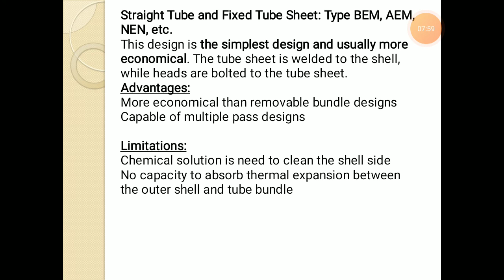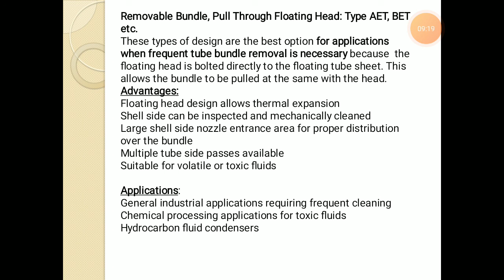Removable bundle pull through floating head type, AET, BET, etc. This type of design is the best option for applications when frequent tube bundle removal is necessary, because the floating head is bolted directly to the floating tube sheet. This allows the tube bundle to be pulled at the same time with the head. Its advantages are: floating head design allows thermal expansion, the shell side can be inspected and mechanically cleaned, large shell side nozzle entrance area for proper distribution over the bundle, multiple tube side passes are available, which is one of the major advantages of the removable bundle pull through head type, and it is suitable for volatile or toxic fluid. The applications of the removable bundle pull through floating head are general industrial applications which require frequent cleaning, chemical processing applications for toxic fluids, and hydrocarbon fluid condensers.